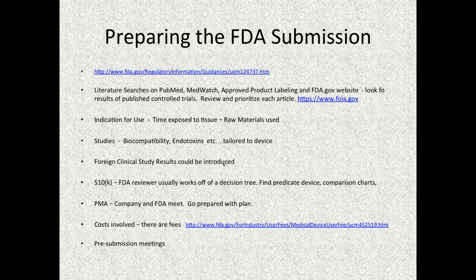Preparing the FDA submission, I put the guidance document link right here for regulatory submissions. Literature searches, you can go through, you can look at freedom of information on the FDA site. If you're doing a 510K, you're entitled to see other 510K submissions. However, they've been redacted, so you'll see a lot of little black marks on them. You won't be able to see everything.